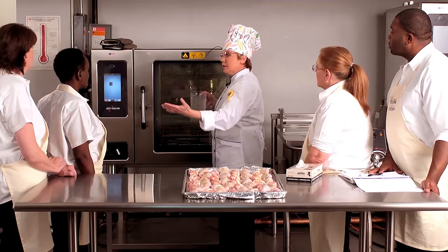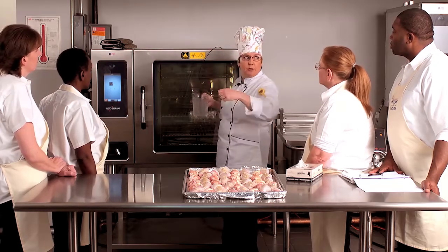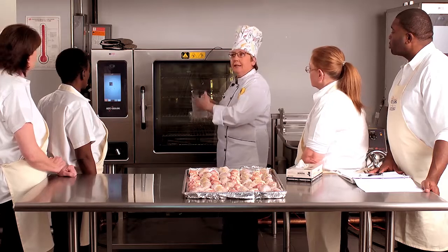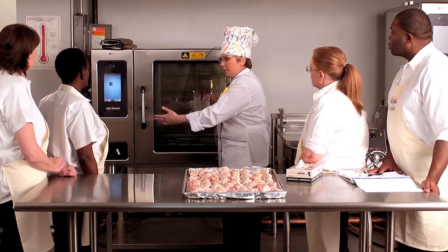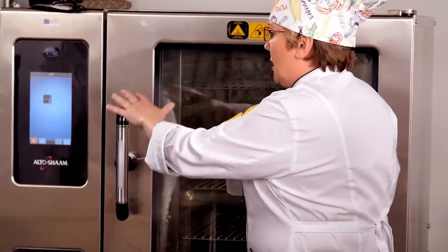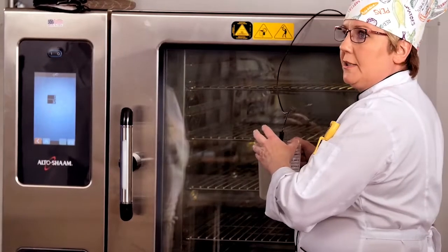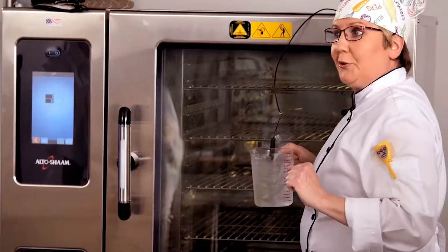Just like with the bimetallic stem thermometer, once the needle stops you would adjust. This works the same way, except it's a digital panel. When the readout stops, you adjust it up or down to 32 degrees.